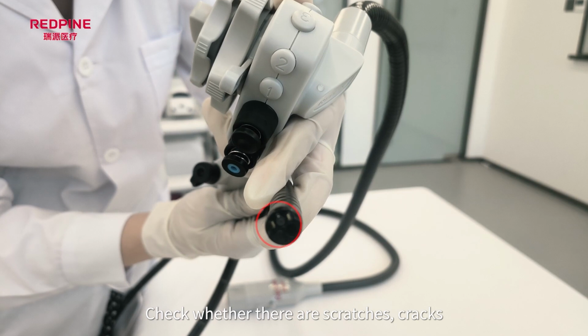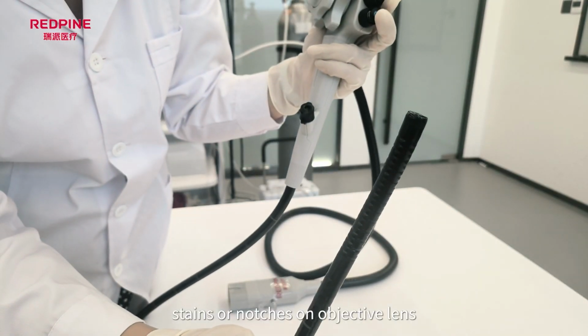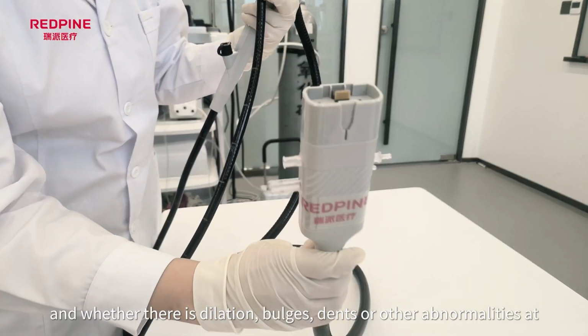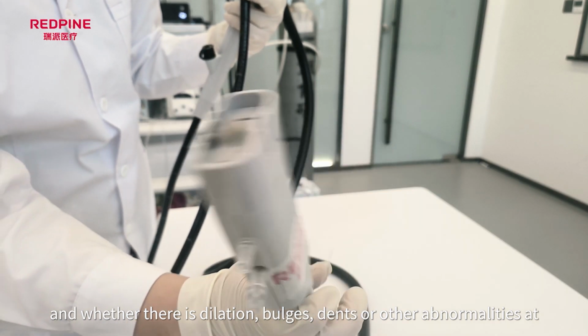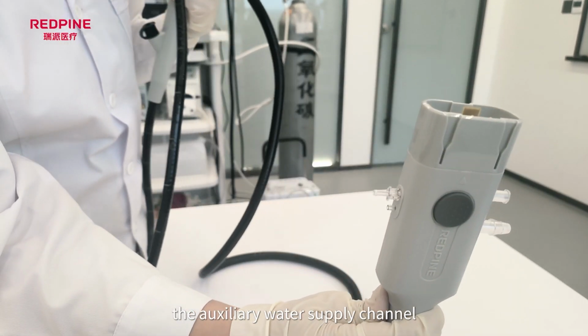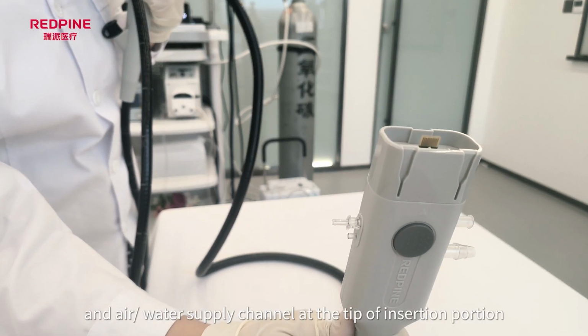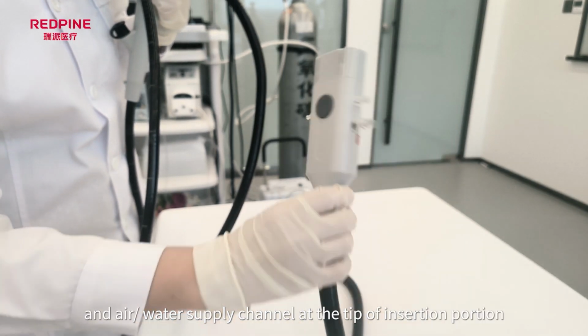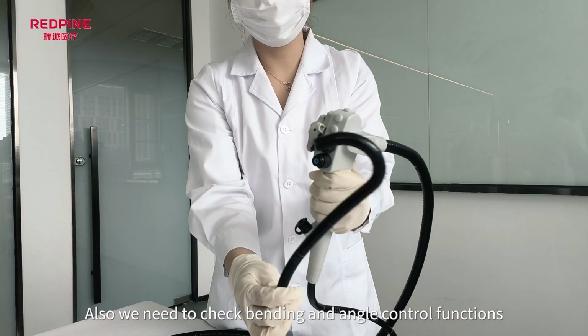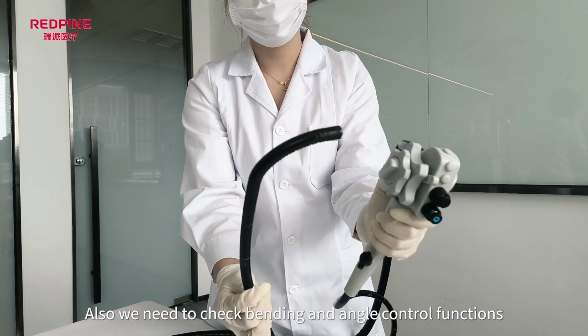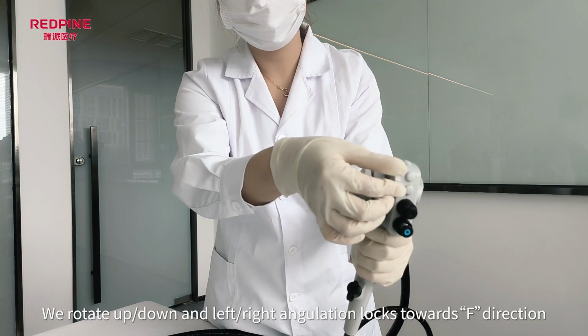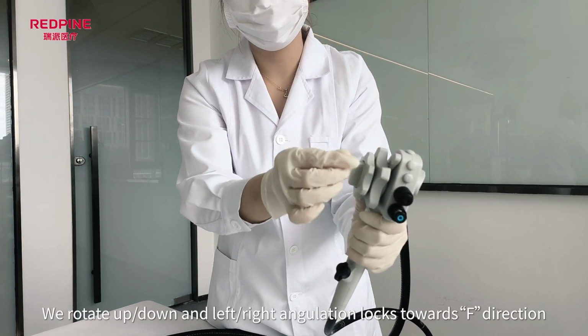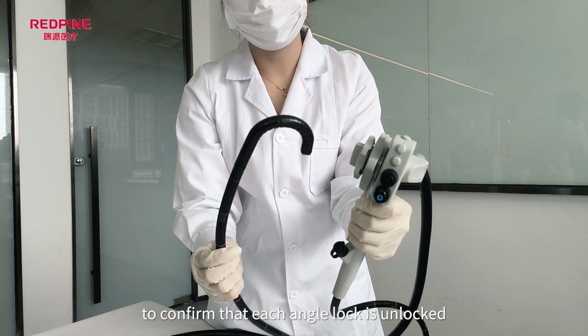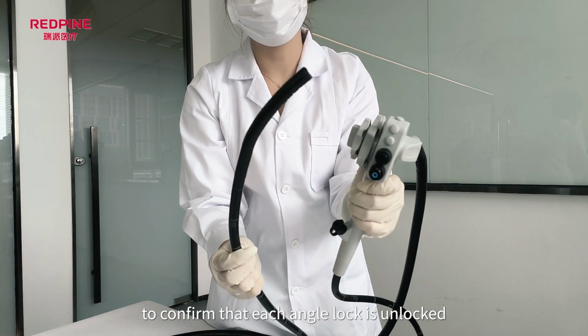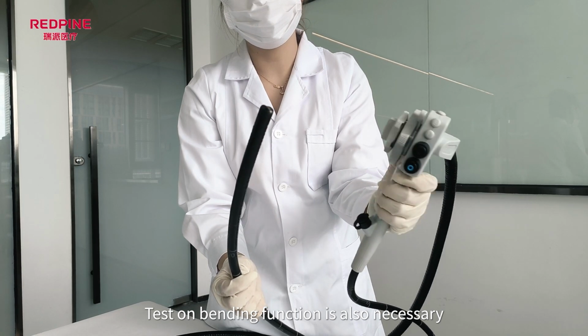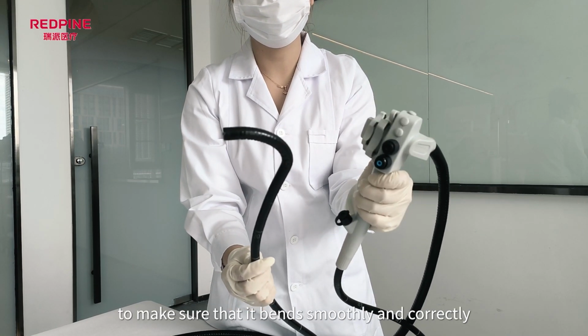Check whether there are scratches, cracks, stains or notches on objective lens, and whether there is dilation, bulges, dents or other abnormalities at the auxiliary water supply channel and air or water supply channel at the tip of insertion portion. Also, we need to check bending and angle control functions. We rotate up or down and left or right angulation locks towards F direction to confirm that each angle lock is unlocked. Test on bending function is also necessary to make sure that it bends smoothly and correctly.